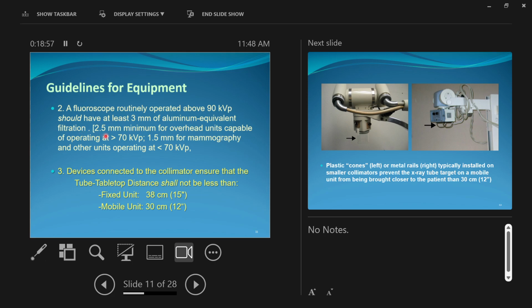Here's what you need to remember. Our machines, which are overhead units, capable of operating above 70 kVp, have to have 2.5 millimeters of aluminum. That's the amount of filtration our units are required to have. Now this is built in and added, but up to 2.5 millimeters of aluminum. This is the stuff that filters out the low energy x-rays in the x-ray beam, stopping them from reaching the patient.